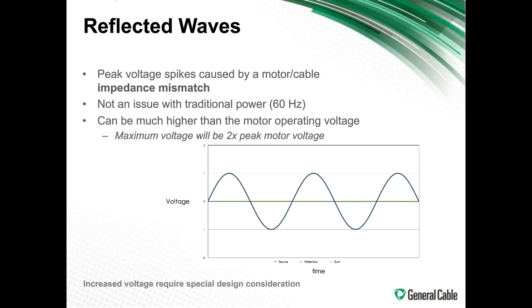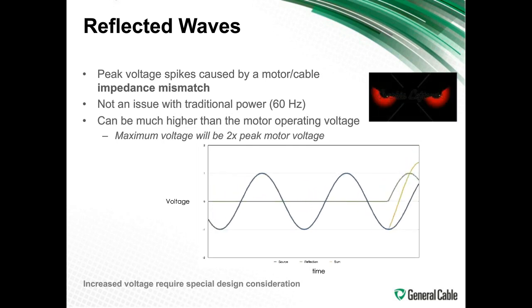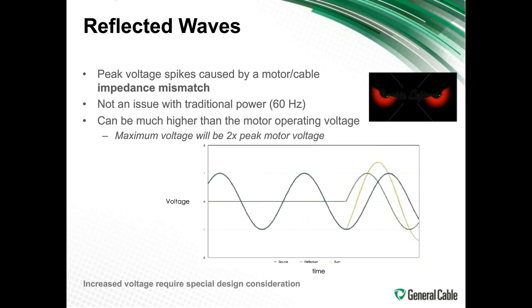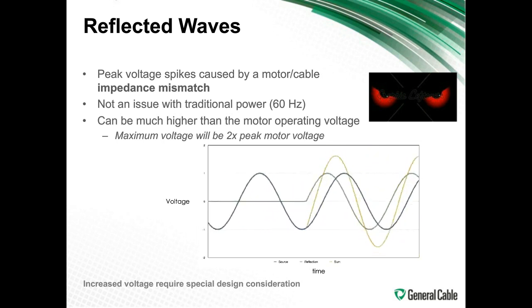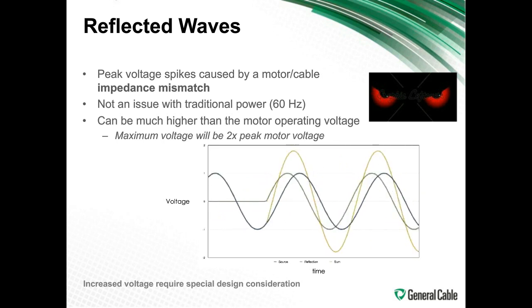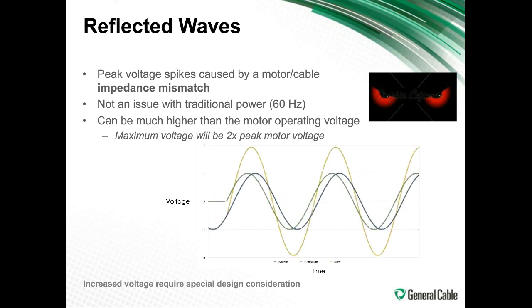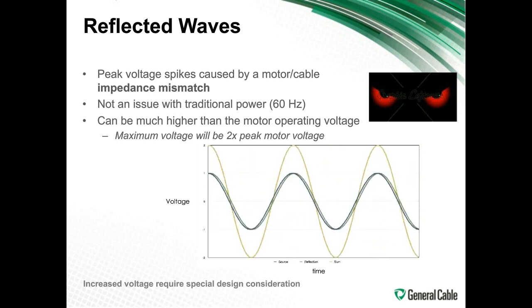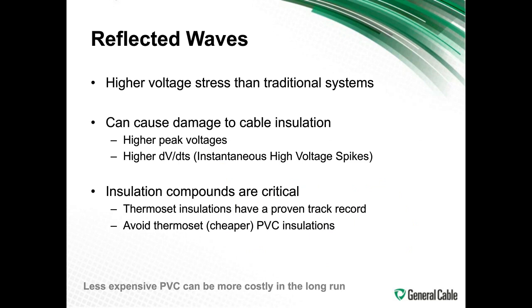And I'm going to show you how this works. The voltage pulses go through, and if you see, I think you can see it move here, then the reflected wave comes back. When the reflected wave comes back and actually gets higher and is not in sync with the others, where they get canceled out, you can actually have double the peak motor voltage. That requires special design consideration to eliminate. Another evil in the system. So this reflected wave phenomenon actually creates higher voltage stress than in traditional systems.